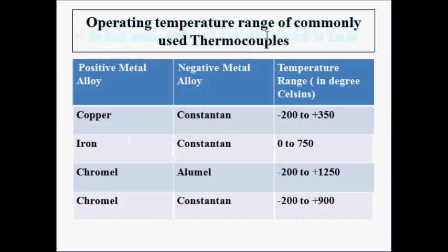The operating temperature ranges of commonly used thermocouples: copper-constantin (positive: copper, negative: constantin) ranges from −200°C to +350°C; iron-constantin from 0°C to +750°C; chromel-alumel from −200°C to +1250°C; and chromal-constantin from −200°C to +900°C. The chromal-aluminium, chromal-constantin, and iron-constantin combinations offer a good temperature range. Depending on operating conditions and requirements, you can select the appropriate thermocouple.